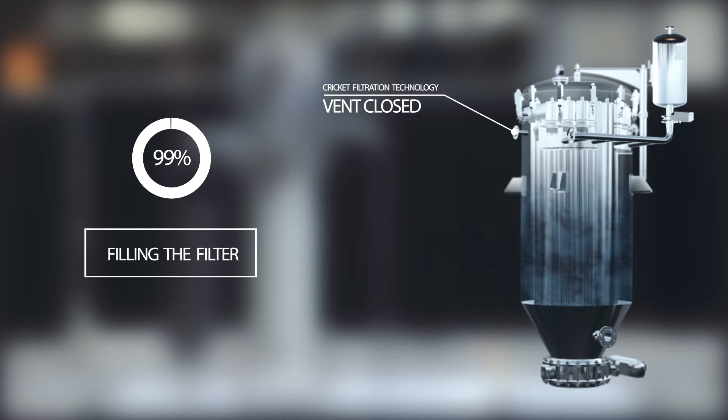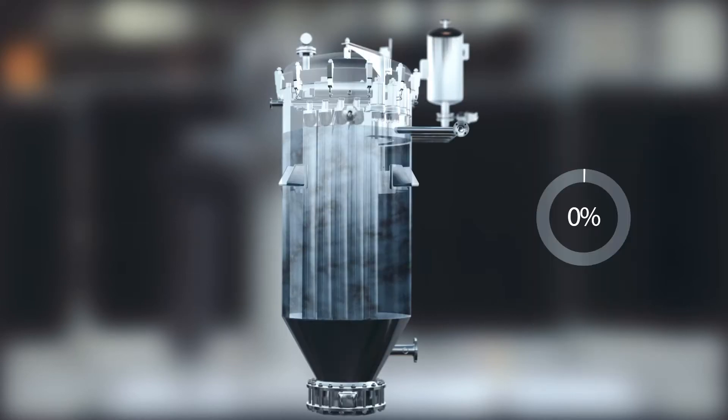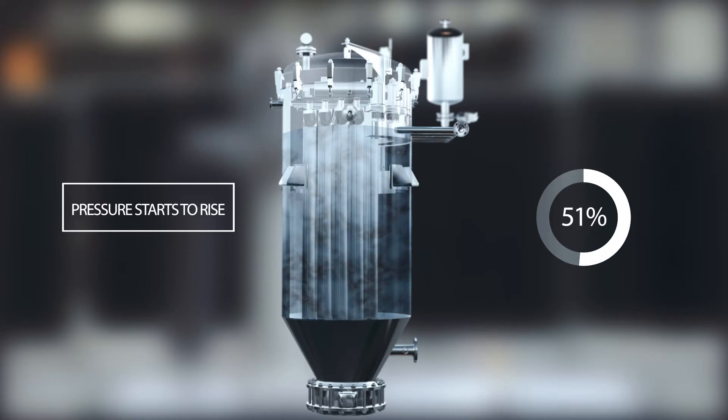The cricket filtration process is a batch process based on cake filtration and is fully automated. By using two or more filters, a continuous feed stream can be processed. Due to its specific cricket-like geometry, the surface-to-volume ratio of a cricket filter is very high.